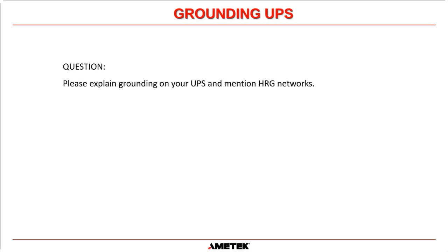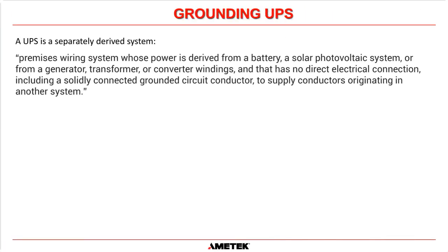Very, very good question. It's something that comes up quite frequently in our day-to-day work. So the first thing that you have to understand is that the UPS is a separately derived system. And the explanation for that is premises wiring systems whose power is derived from a battery, solar voltaic systems, or from a generator, transformer, or converter windings that has no direct electrical connection, including a solidly connected ground circuit conductor, to supply conductors originating in another system. That's the official term for it.